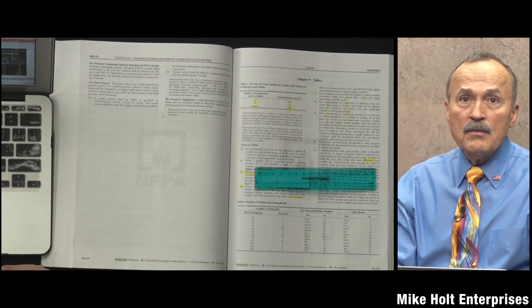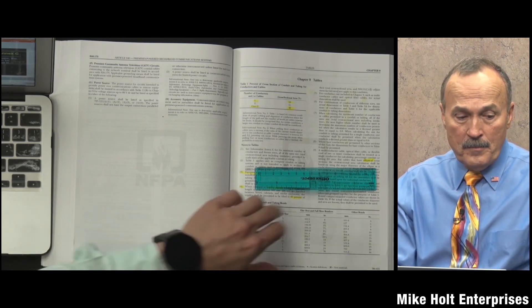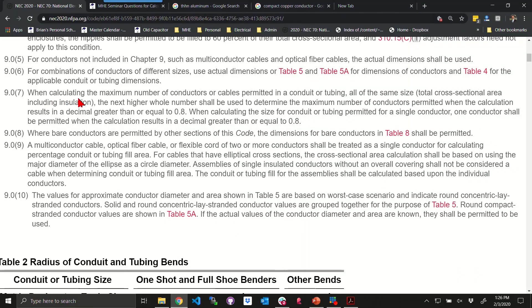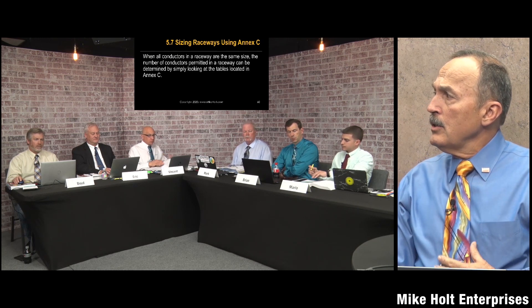Note 7 states: when calculating the maximum number of conductors or cables permitted in a conduit or tubing, all of the same size, the total cross-sectional area including insulation - the next higher whole number shall be used to determine the maximum number of conductors permitted when the calculation results in a decimal greater than or equal to 0.8.